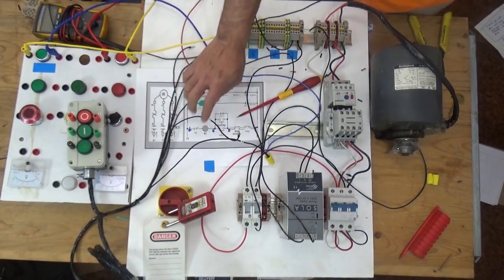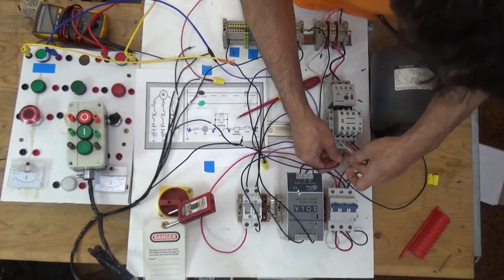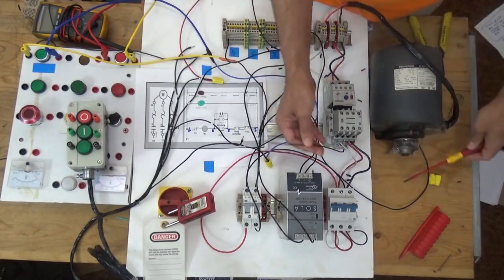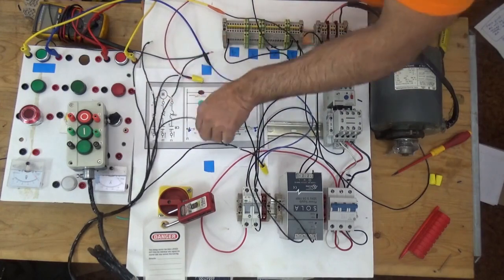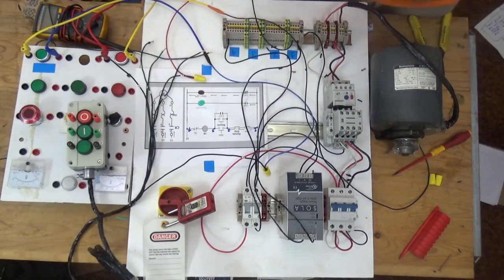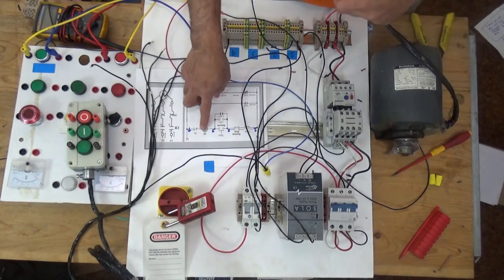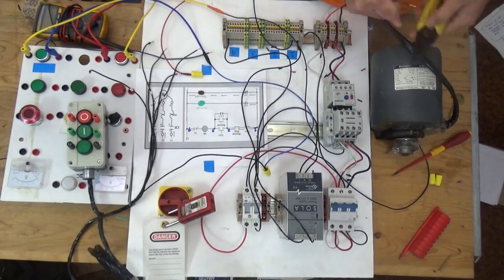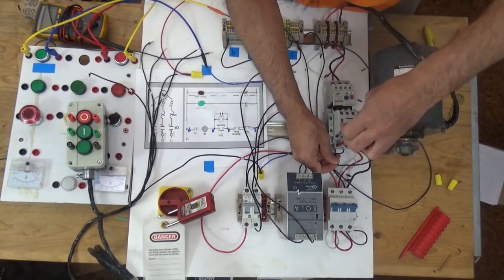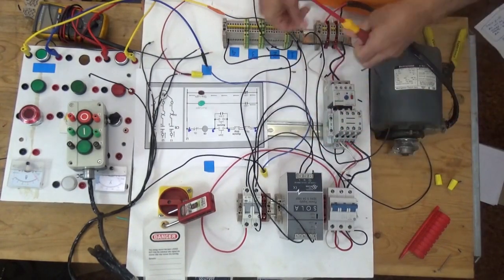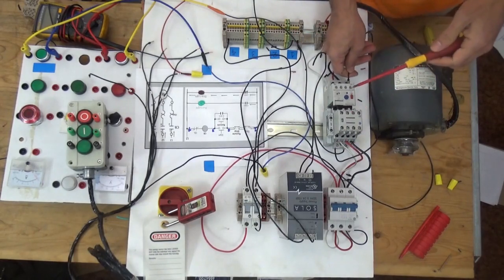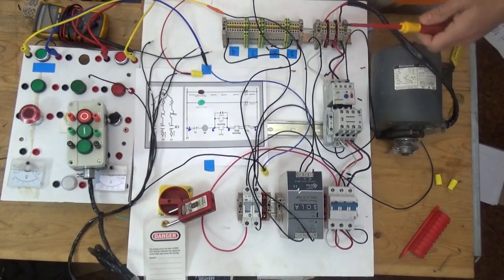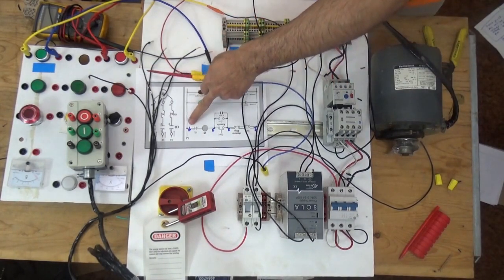Going to our A1 of our relay, of the magnetic contactor. A2 is going to overload relay. Overload relay normally closed here, NC, and from NC going to line four.